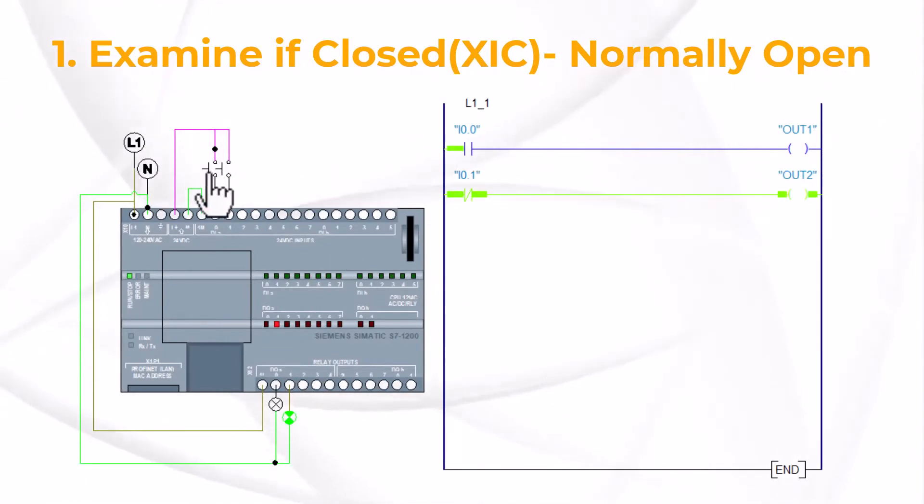XIC, examine if closed or normally open contact. The XIC instruction looks and operates like a normally open relay contact. There is a memory bit associated with each XIC instruction that is linked to the status of an input device or internal condition.